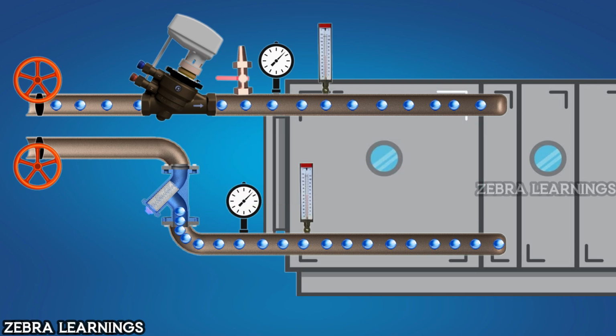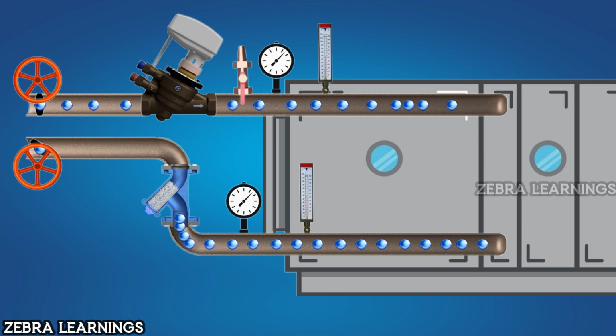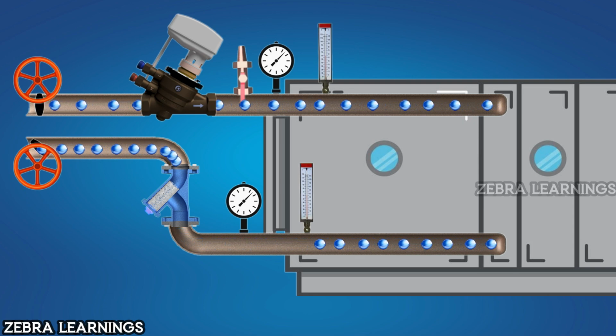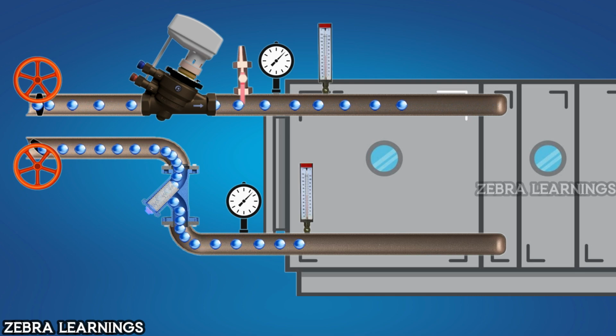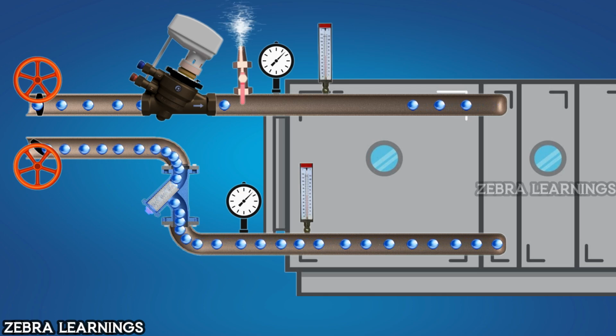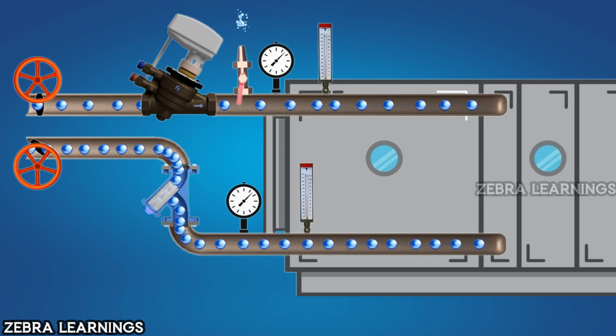Now, we need to slightly open the air vent, located on the return line. Then, we need to slightly open the valve on the supply line. After opening the valve, water will slowly start entering the pipeline. As the water enters, it will push the air through the pipeline towards the return line. When the air reaches the air vent on the return line, it will be released outside through the vent. Initially, a mixture of air and water will be released. Once all the air is released, only water will come out of the air vent. When you see only water coming out, you should close the air vent.